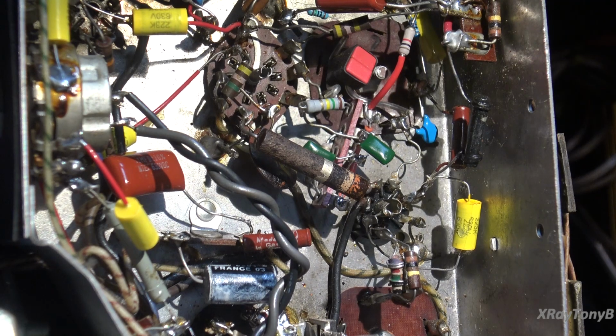Now, what else did that do, and why am I not going over the calibration with you? Well, what happened was, if you get too far out of alignment with your coils, it's what I call, you lose it. Okay, you lose your place. When you lose your place, it's very hard without doing a visual alignment to get things back on center. Using a meter is okay if everything's almost on. So if you have a little bit of drift because capacitances change a little bit over time, it's very easy to do a meter alignment with your VTVM and kind of center it, trim it back up, because everything's peaked out almost already.